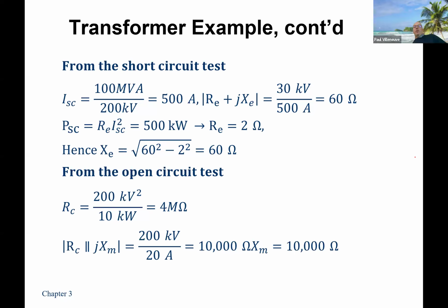So here's the value where we're doing the short circuit test. You can see that we calculated on the high voltage winding. You see it's 200 kV, right? So we connected and measured on the high voltage side because it's using 200 kV. So we get 60 ohms. We do our calculation. And you can use I squared R if you want to do it that way, or you can do the approach where you're solving for Z equals RE plus jXE. It doesn't matter. But I solved 2 ohms here, and then XE is almost the 60, right? Because the 2 is so much smaller than the 60 ohms. You just call it 60.